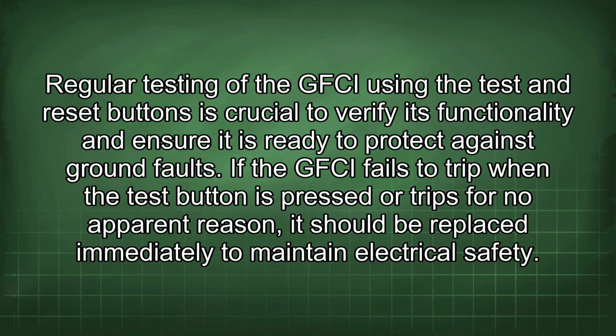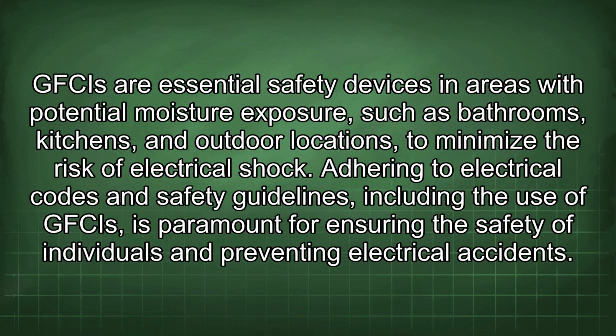Regular testing of the GFCI using the test and reset buttons is crucial to verify its functionality and ensure it is ready to protect against ground faults. If the GFCI fails to trip when the test button is pressed or trips for no apparent reason, it should be replaced immediately to maintain electrical safety. GFCIs are essential safety devices in areas with potential moisture exposure, such as bathrooms, kitchens, and outdoor locations, to minimize the risk of electrical shock.